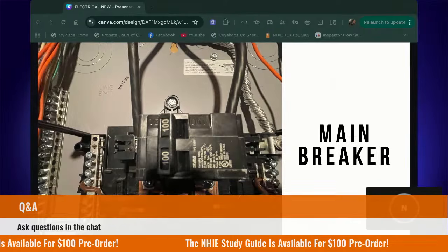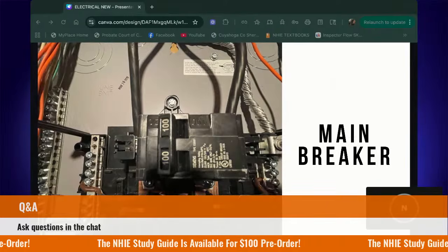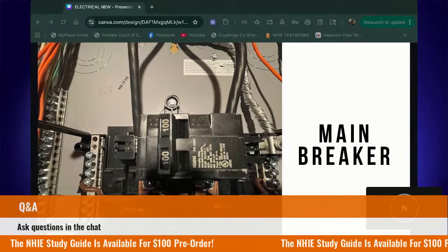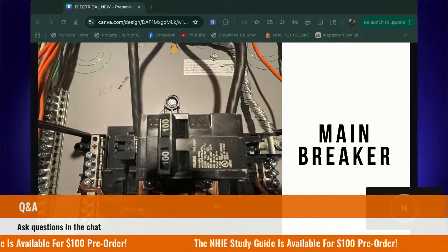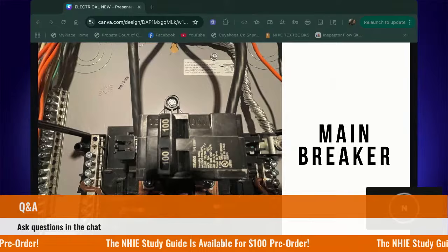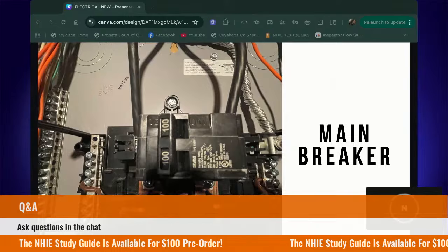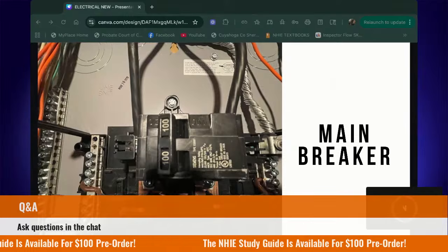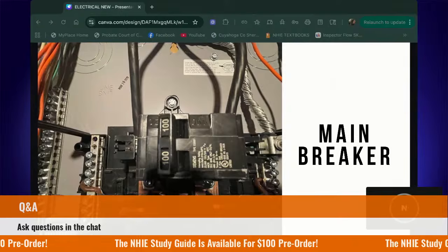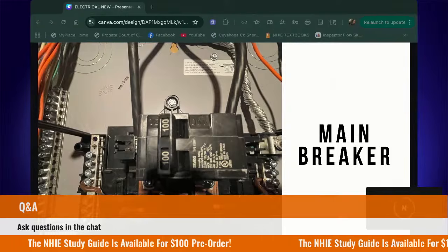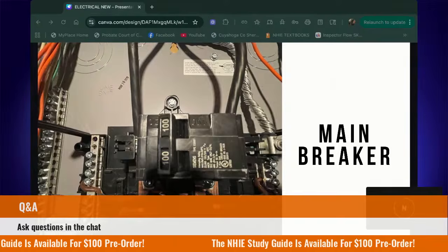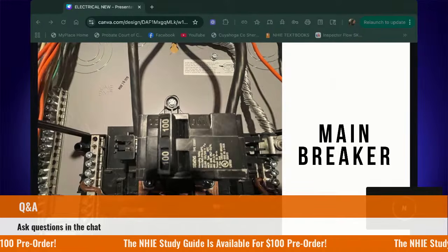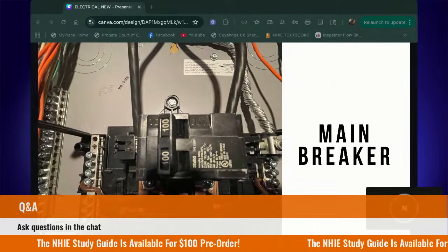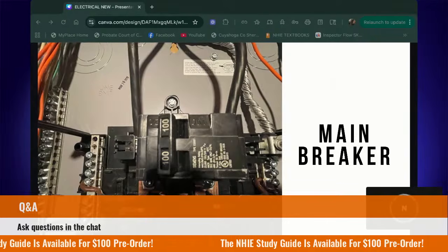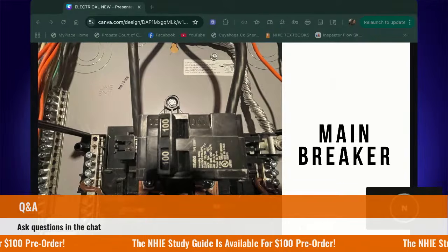This is where you will also find the amp rating. You'll find an amp rating on the main breaker, and that typically is what represents the total electrical capacity that the service can safely carry, which we need it to be a minimum of how many amps? 100. How many? 100. That's correct. A minimum for our residential homes is 100.